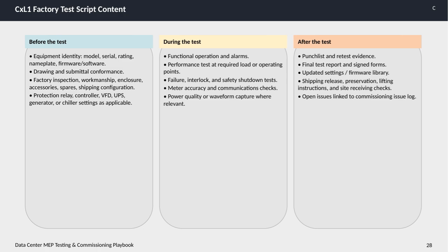After the test is complete, any punch list items should be documented along with evidence of retests where necessary. The final test report and all signed forms must be collected and organized. Settings in the firmware library should be updated to reflect any changes made during testing. Shipping release procedures, preservation methods, lifting instructions, and site receiving checks must be handled thoroughly. Finally, any open issues discovered should be connected to the commissioning issue log to ensure nothing is overlooked moving forward.